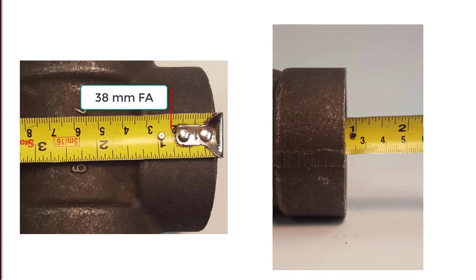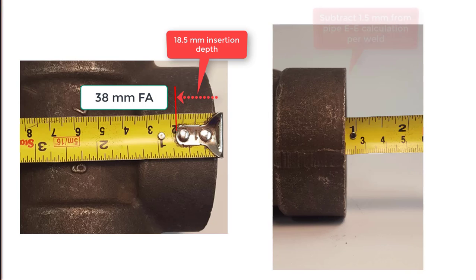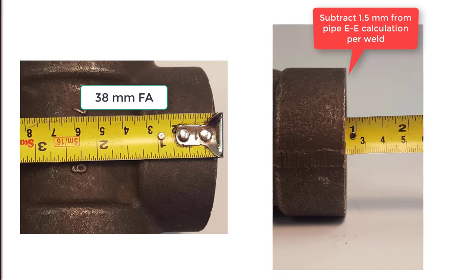But the pipe will only be inserted into the fitting about 18 or 19 millimeters when you consider the expansion gap that we have to leave. So you could change the insertion depth measurement, or I just typically deduct an extra 1.5 millimeters for each welded connection. Typically there would be 2 connections for a center to center dimension, so deduct an extra 3 millimeters from your end to end length for the gaps.